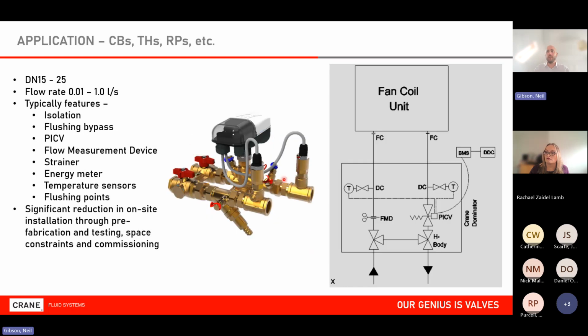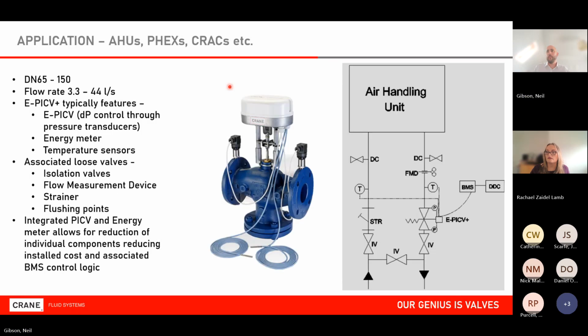So on larger installations with larger flow rates, we can do valve sets which go up to 6 inch in size. But again, we're utilizing existing drain valves with adapters so that the package size doesn't get huge. And usually we've got plenty of space. So yes, the actuator gets larger, but in itself doesn't take up a huge amount of space. There's usually plenty of room for that. So again, we're not making the system cumbersome, but we're generating this energy meter output via the BMS. It's a separate register. And again, we can scale it up from here.